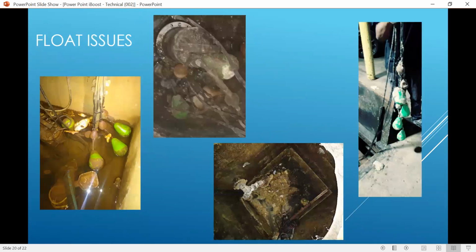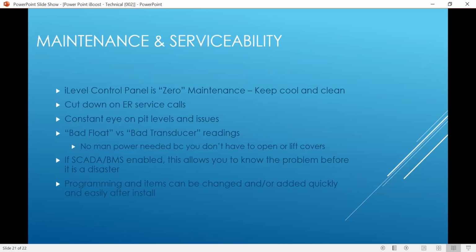Here are some nasty looking floats that we took pictures of to show you why we use a transducer. The transducer just hangs in the bottom of the pit and doesn't have to be adjusted. You set the limit and you put the amount of inches of depth. One of the ones that we just did, which was crazy, we had a sump pit in the Hancock Tower in Chicago that was only 2 feet deep, and there was no way to put a float system in there. When we told them about the level control, we dropped it in there, put the iLevel system in there, problem solved. And don't ask me why they only built a 2 foot deep sump pit. I don't know, but that was the issue, and we solved it for them, and the iLevel came in handy there.